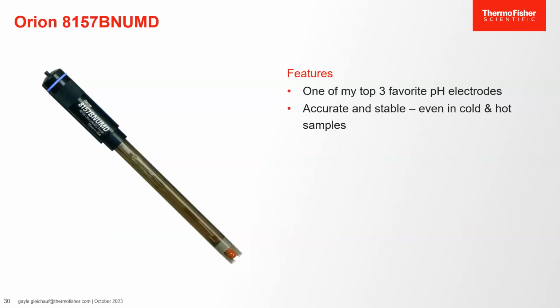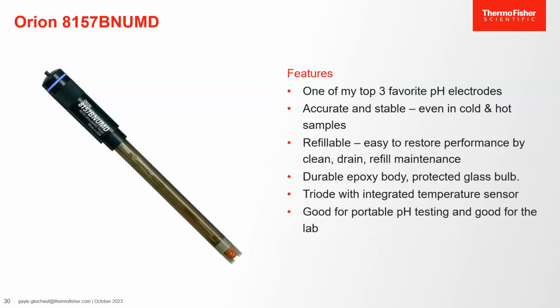And this is the last of my top three favorite electrodes. Like all Ross electrodes, it's accurate and stable, even in cold and warm samples. It's refillable, so it's easy to restore performance by cleaning, followed by draining and refilling the electrode fill solution. It has a durable epoxy body and a protected glass bulb. It's a triode with an integrated temperature sensor. It's a good choice for portable or lab pH testing.